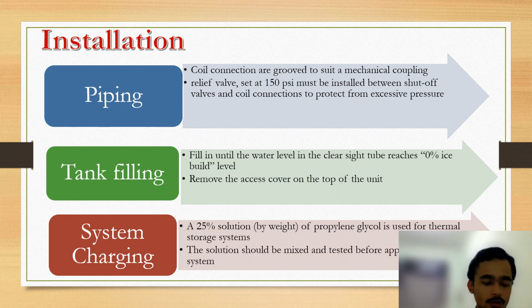I am going to explain about the installation procedure for thermal ice storage. So for the first part is piping. Coil connections are grooved to suit the mechanical coupling, and a relief valve must be installed and set at 150 psi between the shut-off valve and coil connection in order to protect from excessive pressure. So besides the relief valve, a shut-off valve also must be installed, and its function is to isolate the thermal ice storage from the system.